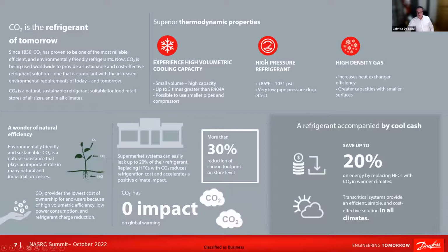It has superior thermodynamic properties, with a high pressure refrigerant, high density of the gas, and high volumetric cooling capacity. It has zero impact on global warming, with more than 30% reduction of carbon footprint at store level for supermarkets that adopt it as a refrigerant, and it can provide energy savings, a reduction of energy consumption of up to 20% also in warmer climates. Of course, it's up to, because it depends on a lot of factors of the system design and which solutions have been implemented, but these are the results that can be achieved.